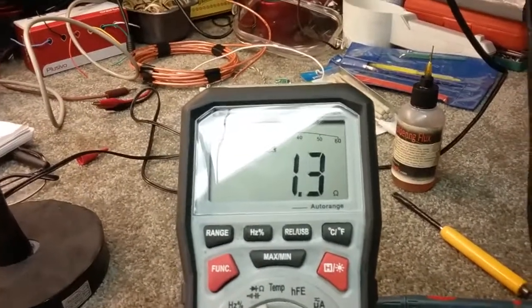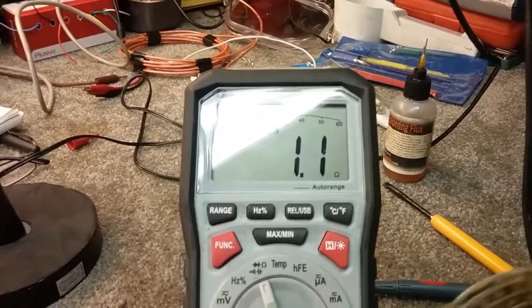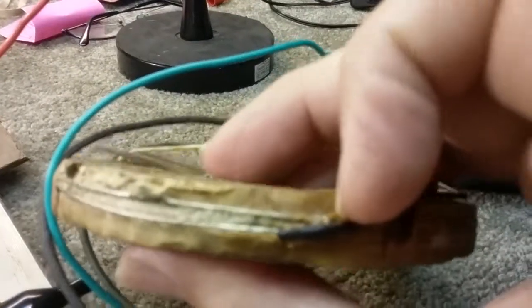It's about 1.3 ohms - it's a dead short, totally shorted, and the wire in it is corroded. You see all that green corrosion. I tried to identify where it's shorted, but I can't. I moved the wires around. It's insulated here, so I know they're not touching, and I checked that. I tried to find it, but it's somewhere inside the actual lamination that it's shorted out.